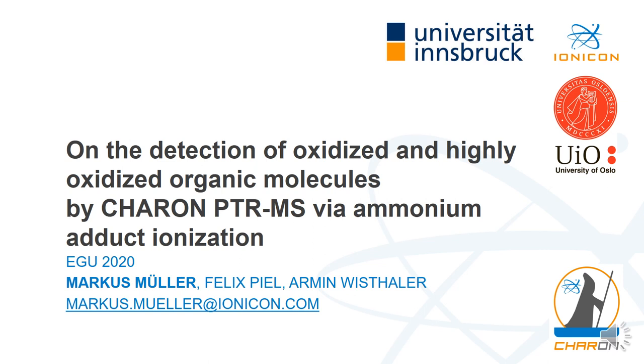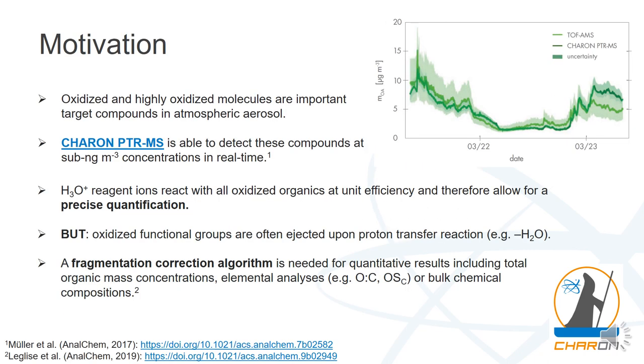Welcome to the EGU 2020 display on the detection of oxidized and highly oxidized organic molecules by CHARON PTR-MS via ammonium adduct ionization. Oxidized and highly oxidized molecules are important target compounds in atmospheric aerosol — they define the phase and production of the aerosol. CHARON PTR-MS is able to detect these compounds at sub-nanogram per cubic meter concentrations in real time. H3O+ reagent ions react with all oxidized organics at unit efficiency, allowing quantitative measurement.